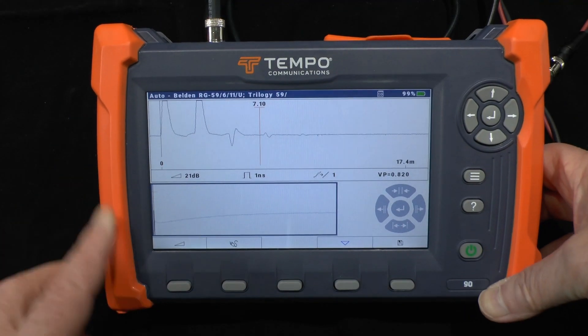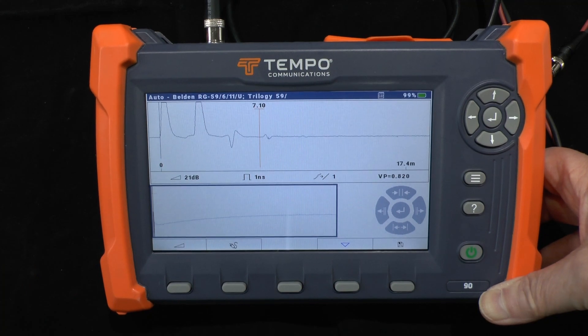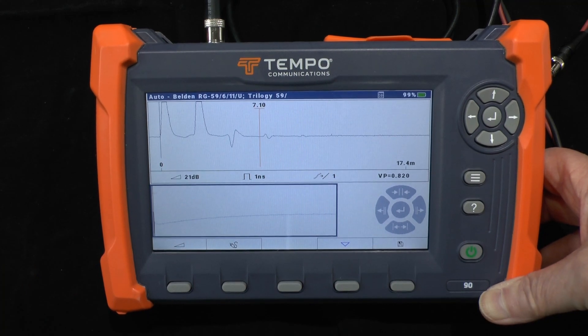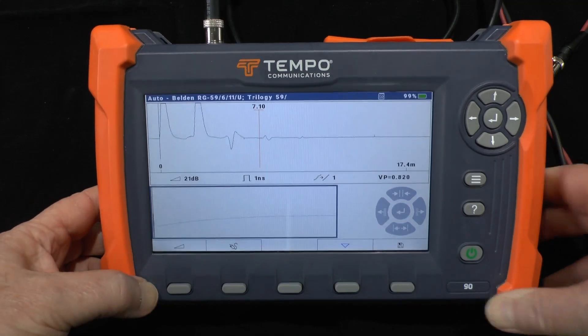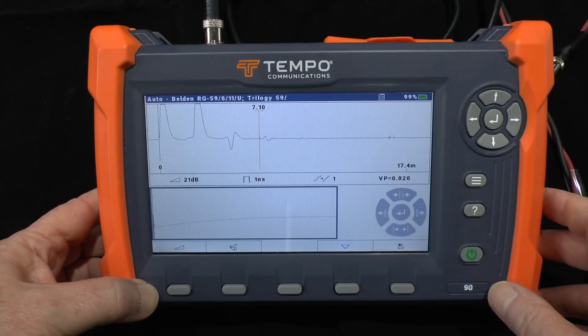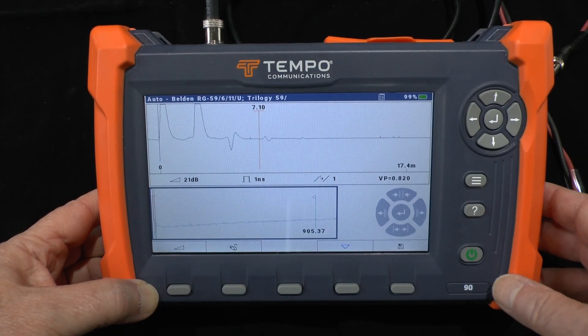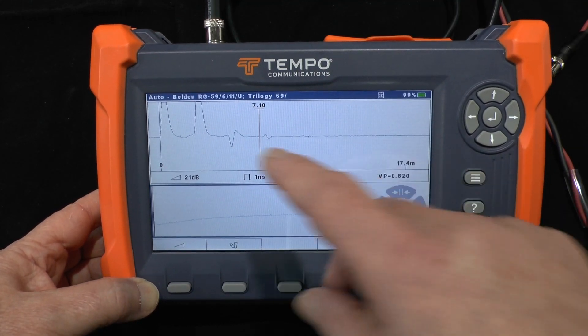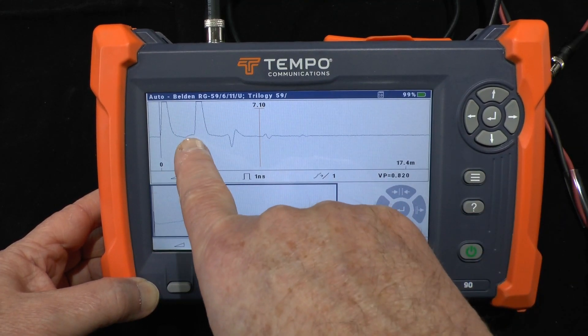I'm going to try and explain how you can use a TDR like the CS90 to help diagnose any trouble with cables like a heating mat or just general cables. The first thing to remember is a TDR is going to show you a reflection from every change of impedance of a cable.